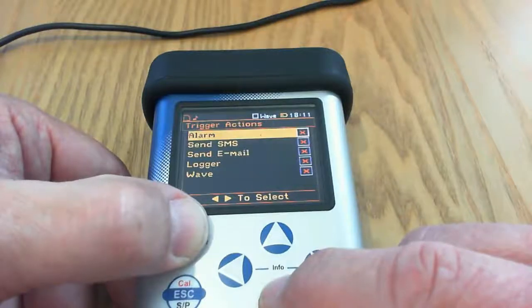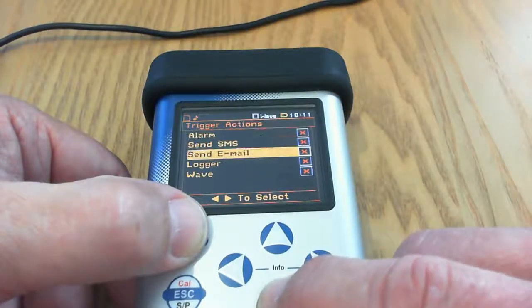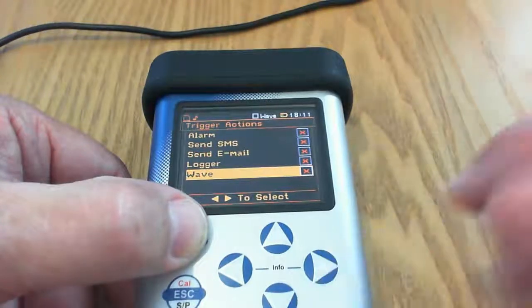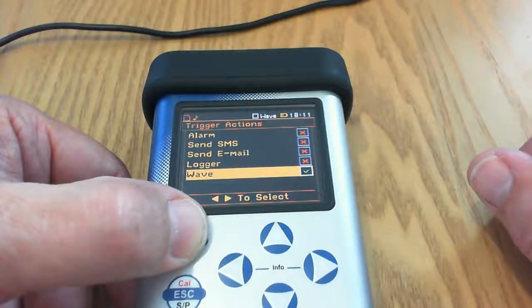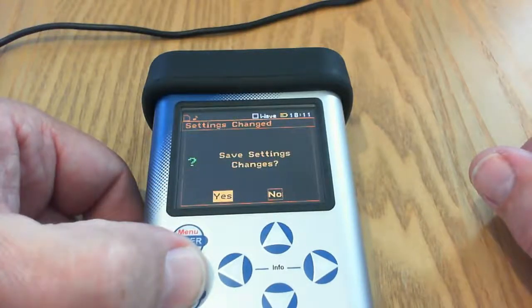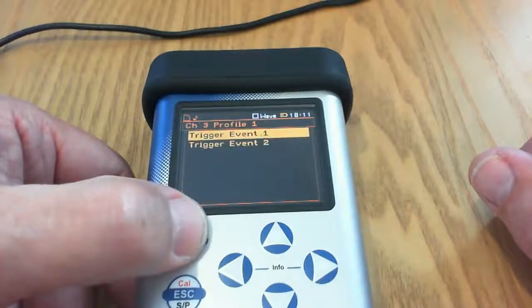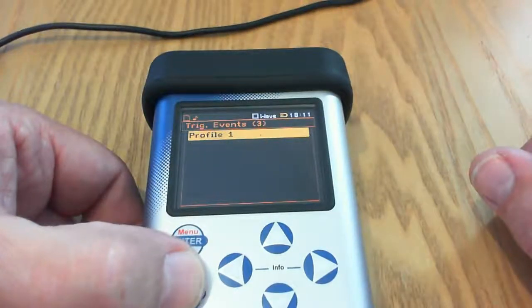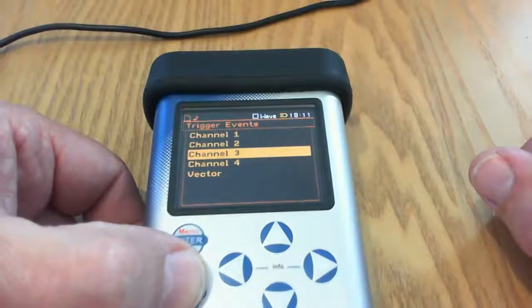Then the trigger actions you can set here. Let's go down to wave. So I want to trigger a wave recording from that trigger level. Press enter to accept those parameters and now escape back to the events setup.